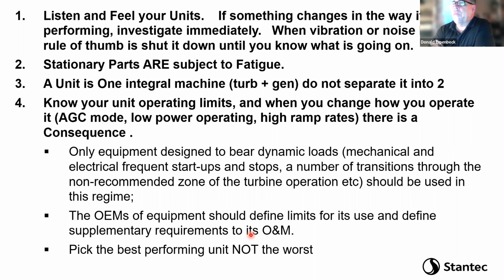One of the other lessons learned here is that stationary parts are subject to fatigue. Before this, a lot of the fatigue design used in hydropower turbines ignored the stationary bolts and anchor bolts—no one was checking them. After this event, a worldwide call went out to check head cover bolts, and projects all over the world found major fatigue cracks in their stationary bolts.